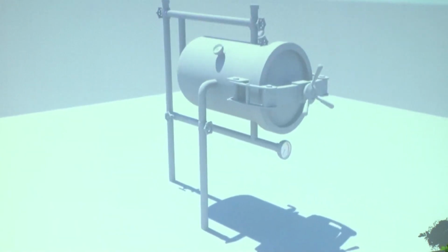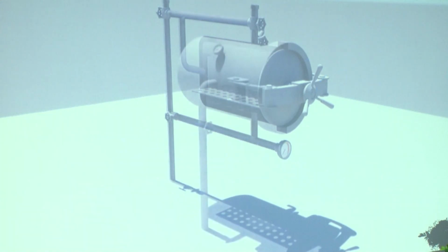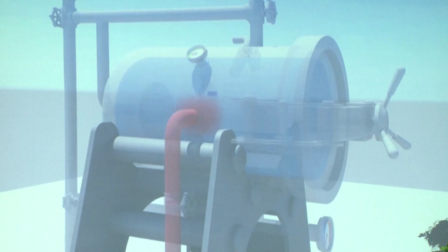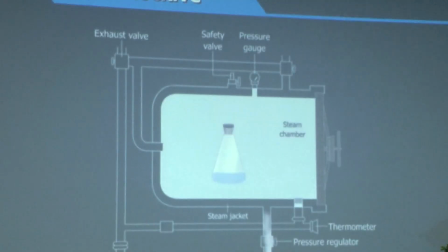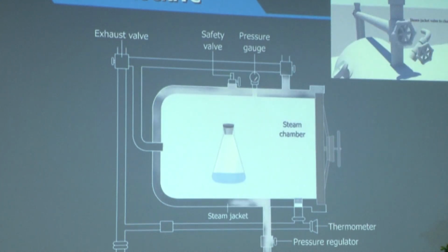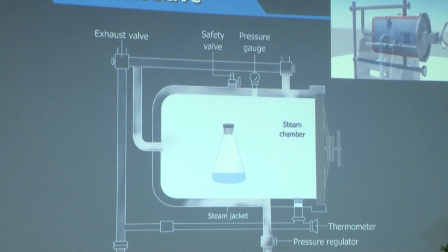So the autoclave, whatever autoclave it is, has 2 jackets, an inner jacket and an outer jacket, with a series of valves. These valves let in the steam inside the autoclave in a graded manner for the temperature to rise and sterilize your instruments. Most of the time, these valves are the ones which cause the leak, which causes a failure of the sterilization cycle. So you really need to know these valves, how they function, change the gasket or whatever is possible to ensure that they work well.